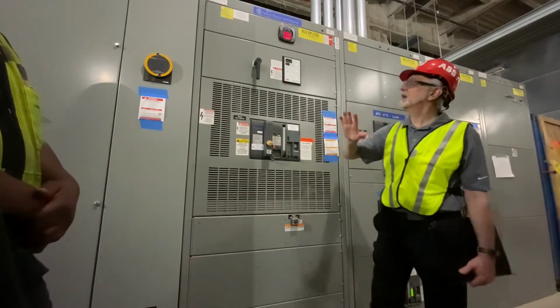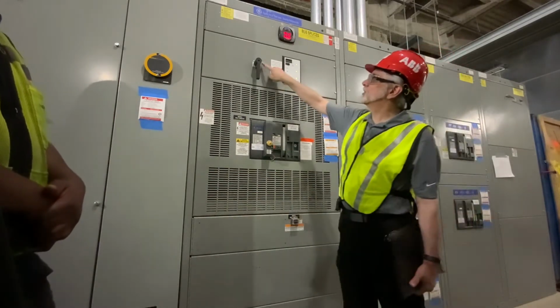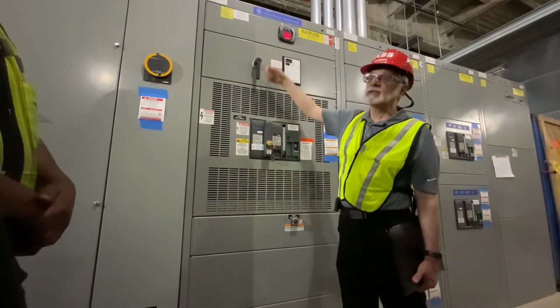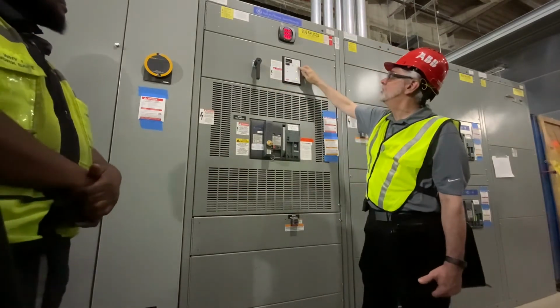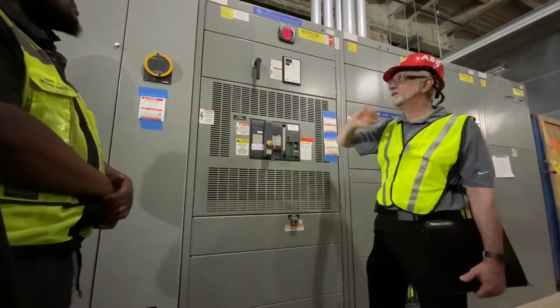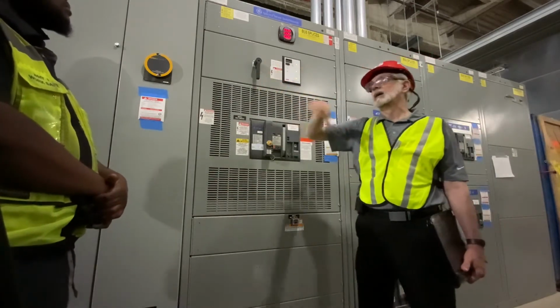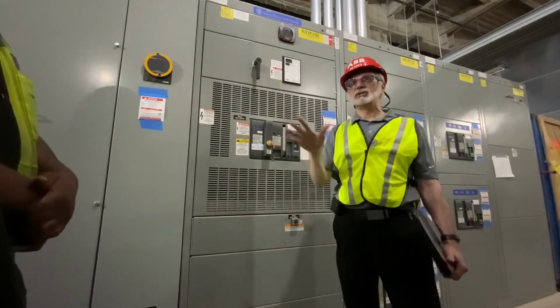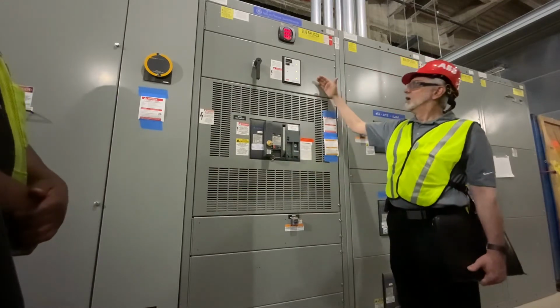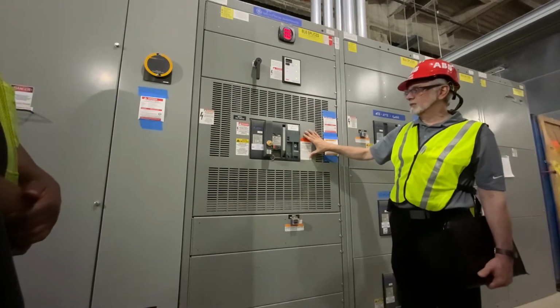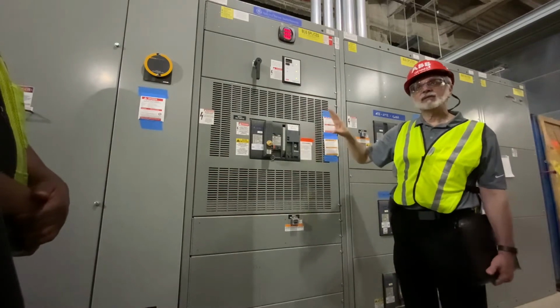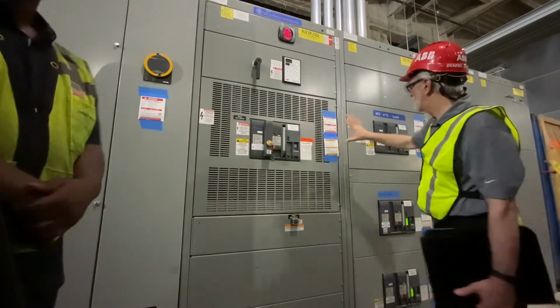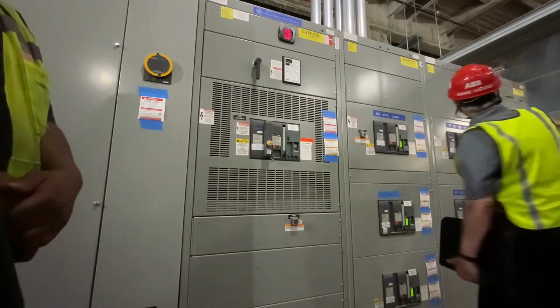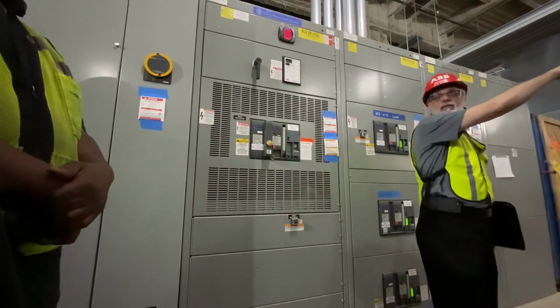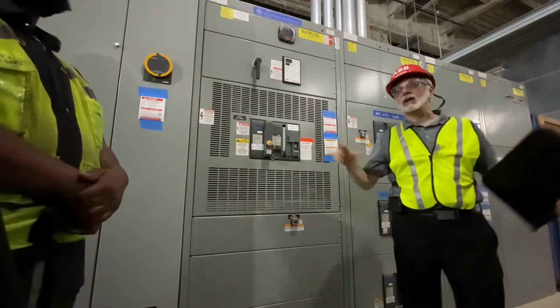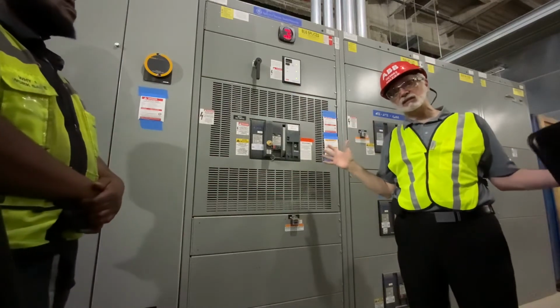But the main thing you want to do is make sure it's in the on position like it is now, so the handle is vertical. And number two, just make sure that your lights are green. If either one of those conditions is bad, double check everything on that. From there we go to the main breaker. This particular type of lineup is a main with some distribution section and then a tie over to the other piece of equipment. So this is what we call a double-ended unit substation.